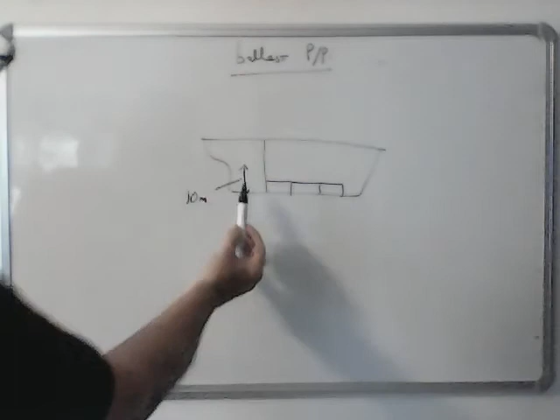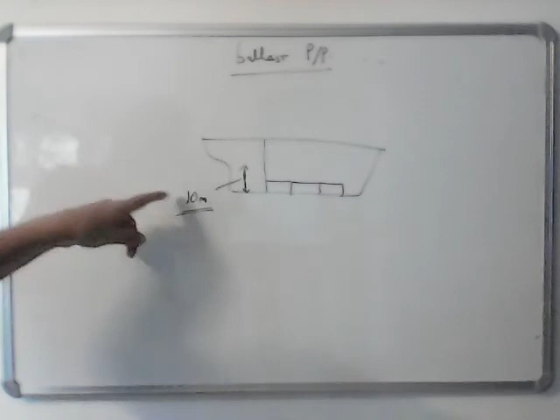We will do one more topic now, ballast pumps. Now, first, if this is the ship and you have some double bottom tanks also to be deballasted by the ballast pump. So first let's understand the position of the ballast pump in the engine room. How high can it be placed vertically? Maximum height. The answer is 10 meters because by vacuum you can only suck up to maximum 10 meters because the atmospheric pressure is 10 meters of fresh water.